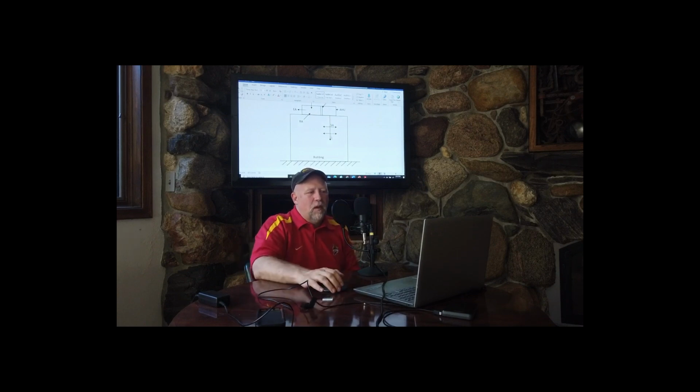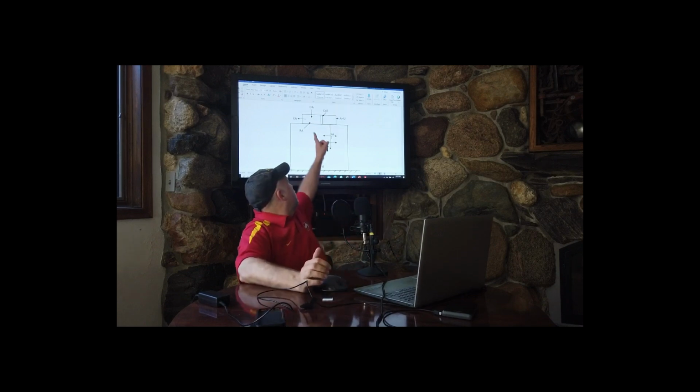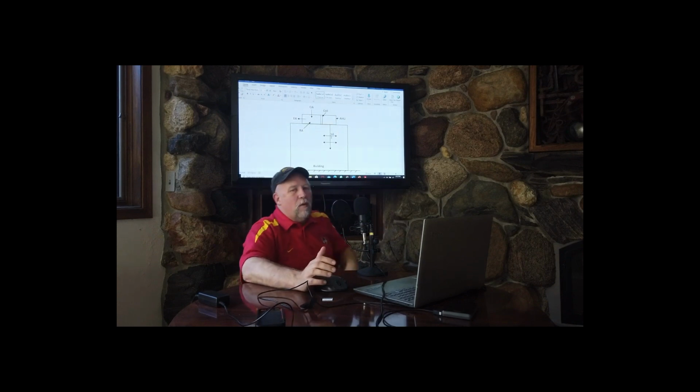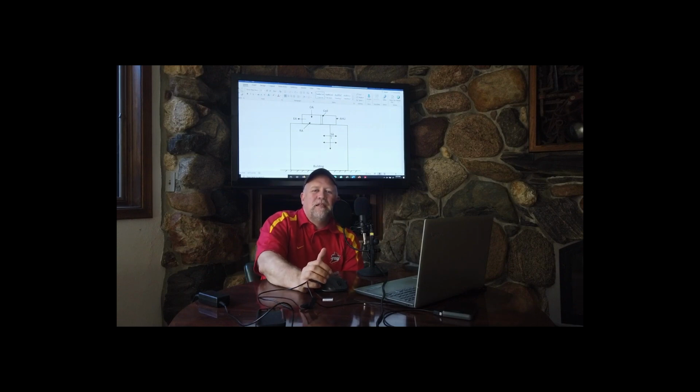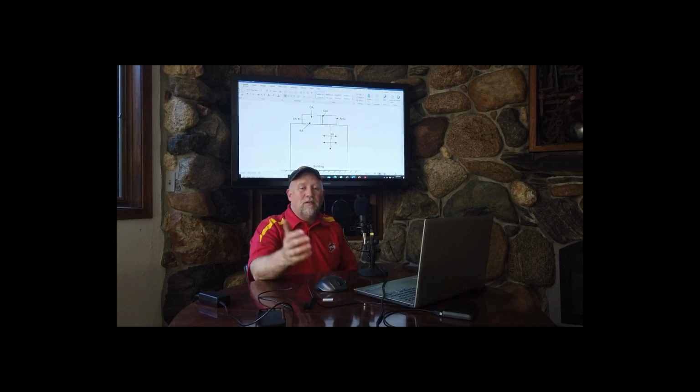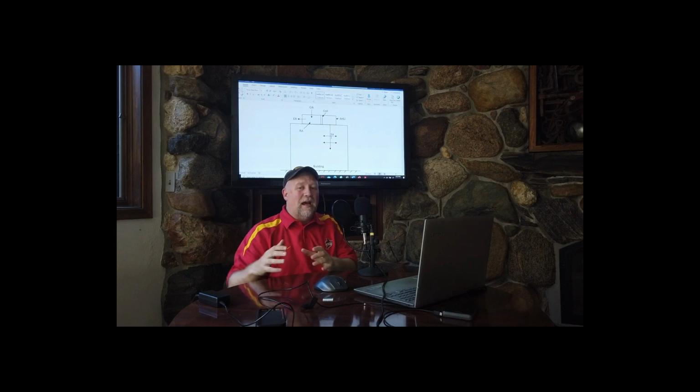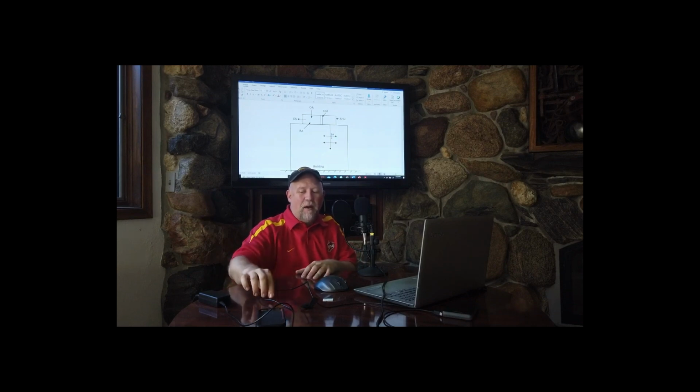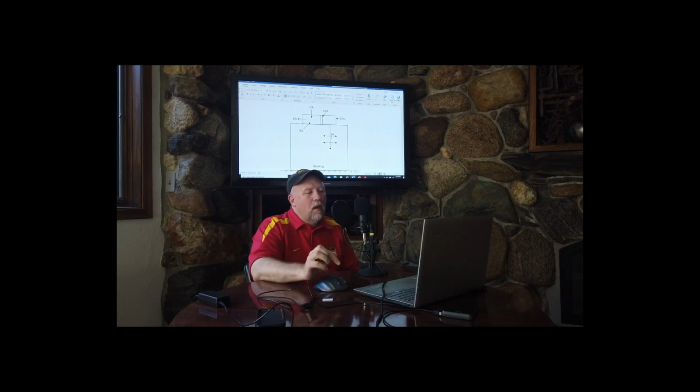loads. Right? Now, once we return that air, we're going to exhaust some of it and bring in some outside air. Remember, the amount of air that we're going to bring in is based on ASHRAE Standard 62. There's that table that I handed out. It's one of the tables in the handout packet that we looked at earlier. That'll tell you how many CFM per person that we need.